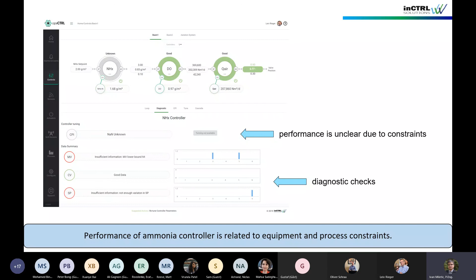Here's an example of how this works for a DO controller. We're analyzing the entire cascade, starting with the ammonia controller, but now looking at the DO controller and the one below it. Our approach evaluates controllers further down in the cascade first - if their performance is reasonable, we can then evaluate the higher-level controllers. In this case, we evaluate the DO controller because the air controller is performing well.